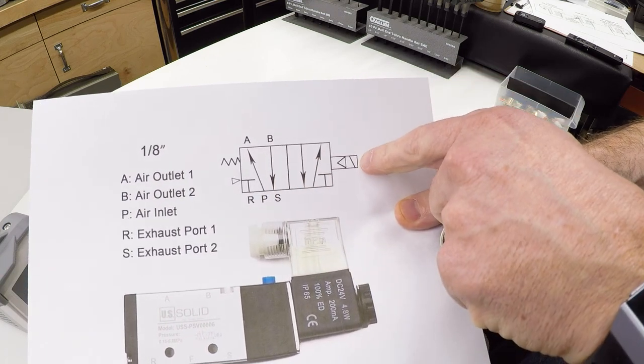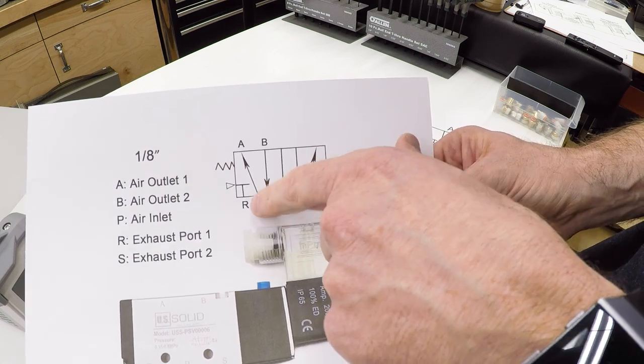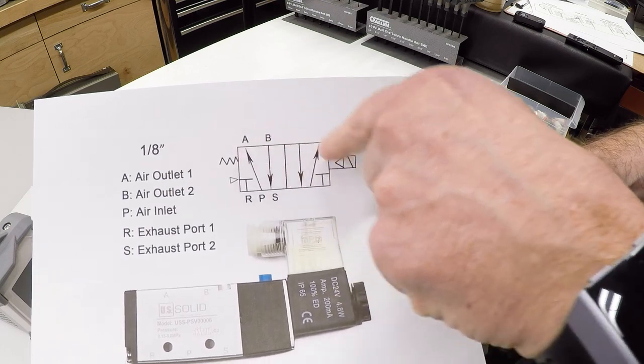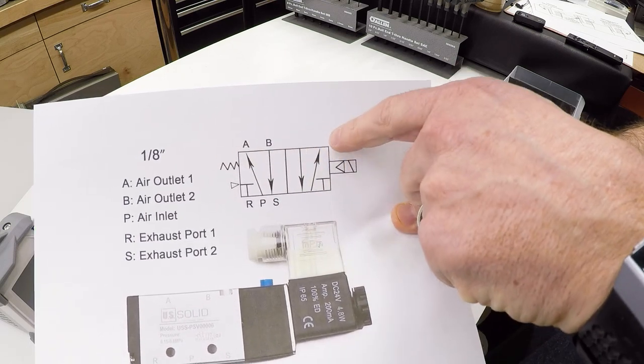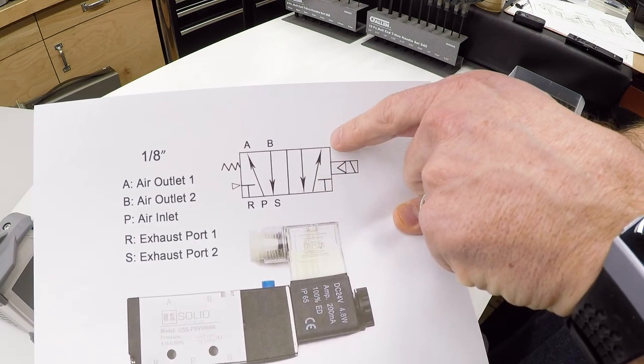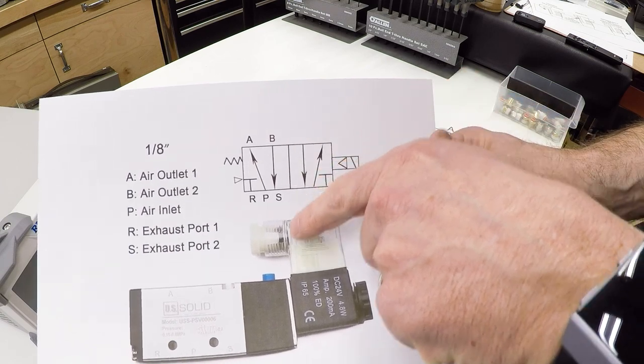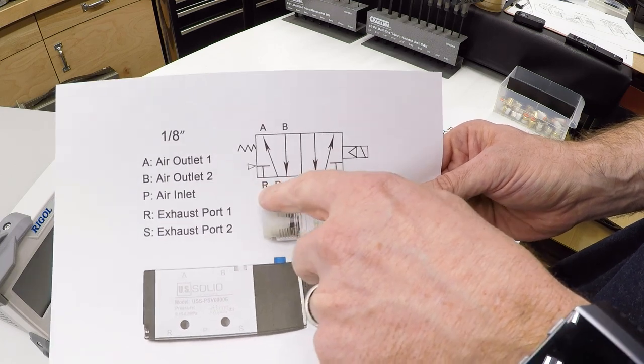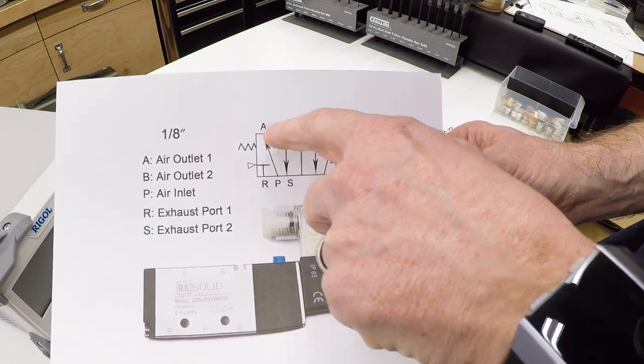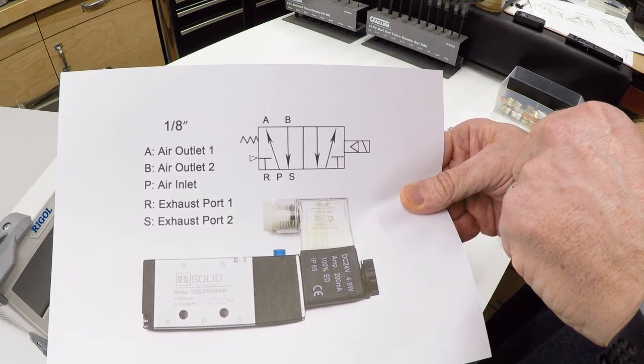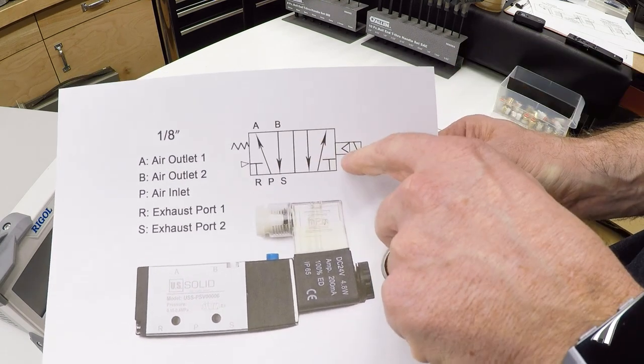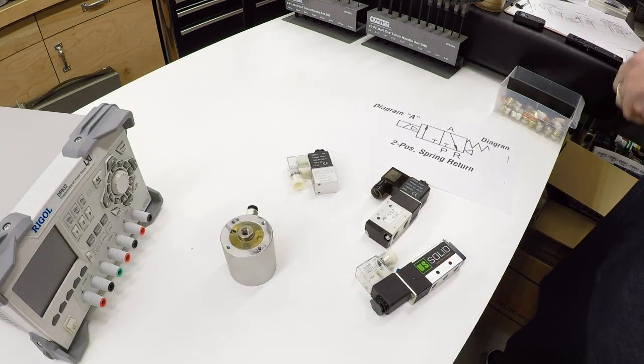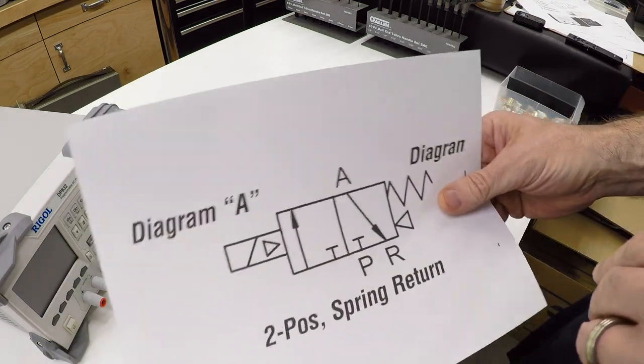Then when you activate the solenoid, it switches to the other state. Where the pressure was going to the A side, now the pressure will go to the B side. Pressure goes to the B side, pushes the cylinder the other way, and the other end of the cylinder is open to the atmosphere. So you provide pressure in and two exhaust ports, and then these two hook to the two ends of the cylinder.